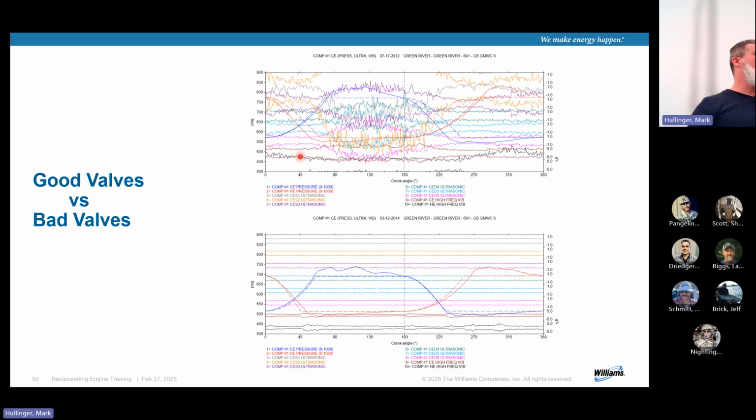That's screaming at you, but there's stuff in the gray areas that you have to make judgment calls on, okay? So to give you an idea of why we should change valves, the operator at this time was rebuilding old style valves, so the metal plate valves, and there was just a goodie box over the years of spare parts and they just kind of rebuilt them. And this particular operator called those new valves. And I thought, man, that's what a new valve looks like. I thought he had bought new valves. And I come to find out with a little bit of talking that it's just rebuilding old style valves, right?